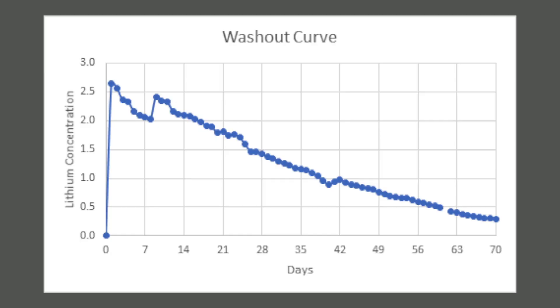To undertake a test on any tank, we stop the feed into the tank, dose a slug of lithium — typically enough to reach 3 mg per litre in fully mixed conditions — we then sample at the outlet at regular intervals, intensively at first and then reducing over time, for at least 3 hydraulic residence times. That's the expected residence time within the tank, accounting for the flow and volume at design. This typically generates a graph much like the one you can see below.